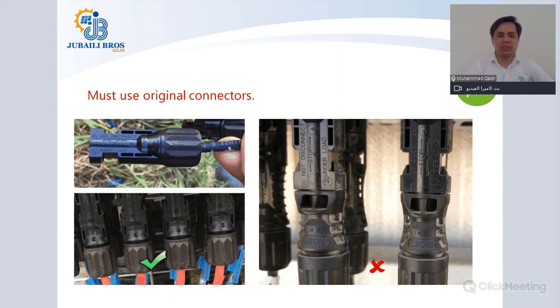Must use original connectors. Now, this is also a very common error made by solar contractors. The connectors which we provide inside the inverter package, they use, and due to a wrong connection, they dismantle it, throw it away and try to use a third-party connector. The third-party connector could be anything from the market, which HUAWEI strongly advises against. It tells you not to use connectors from a third party, which is not from the same brand as the HUAWEI connector itself.